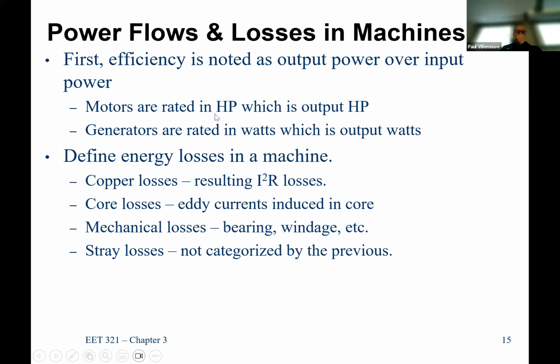Motors are rated in horsepower—that's the amount of output power they can put on the shaft. They don't care about the input power, only output power, because mechanical engineers just want to say, I need 97.6 horsepower to drive this load. You need to specify what the feeding system can handle given the motor's inefficiencies. Same thing here—your generator is rated in watts.